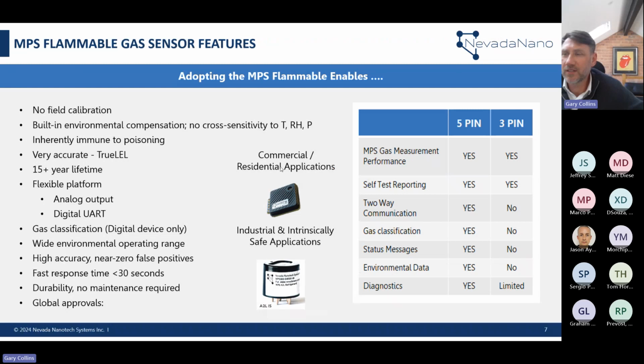Looking at the sensors themselves, we offer them in effectively a 3-pin or a 5-pin version. You can take an analog variant, very similar to a traditional Pellistor sensor, or you can take a 5-pin, which gives you a digital output. I'm not going to go through every single line item since I've already talked about it, but effectively, as I said, no calibration is needed, and we do the environmental compensation for temperature, pressure, and humidity.